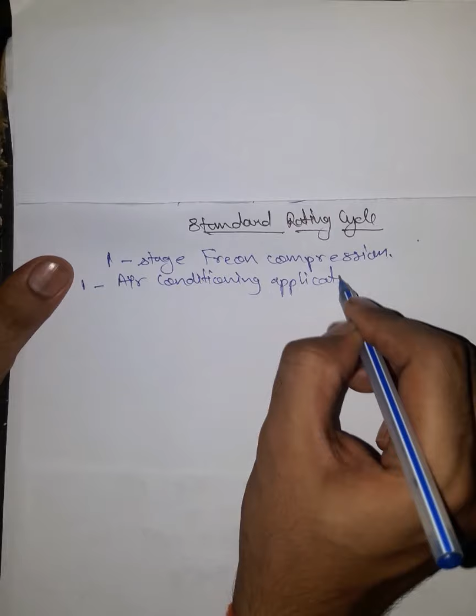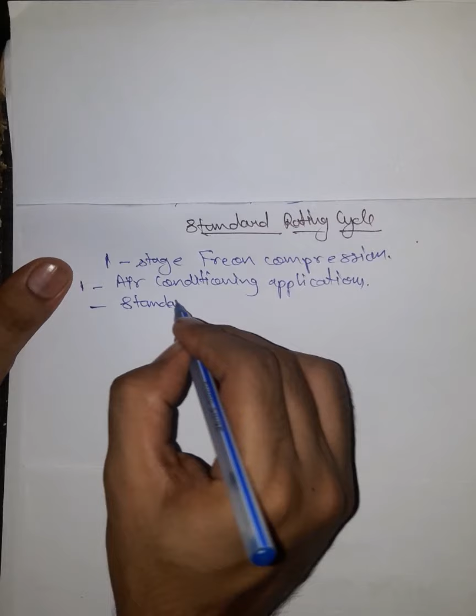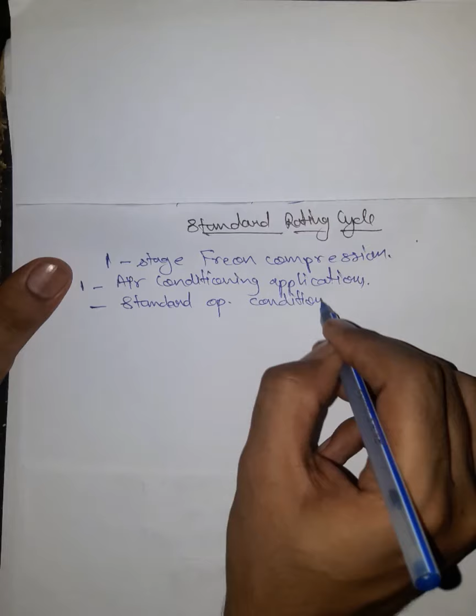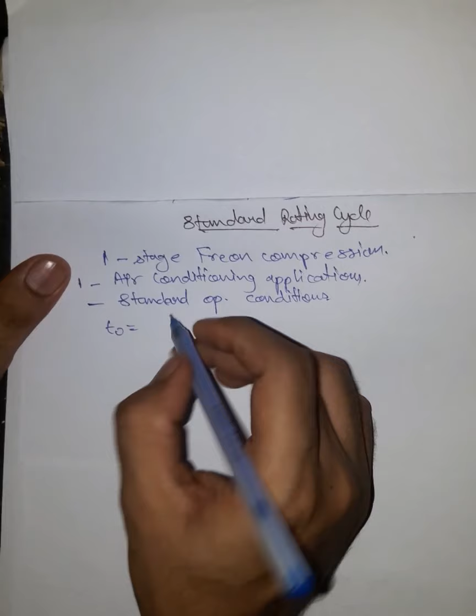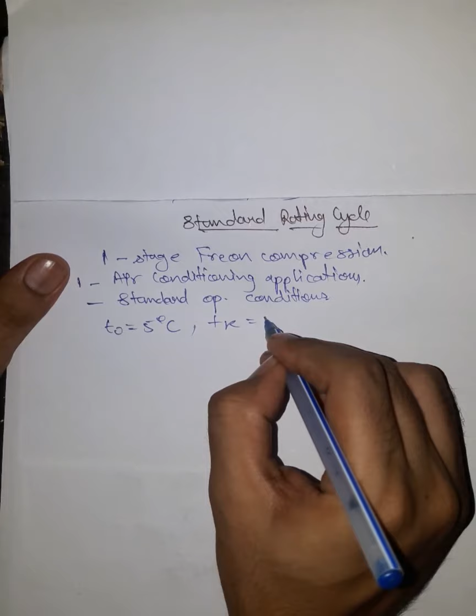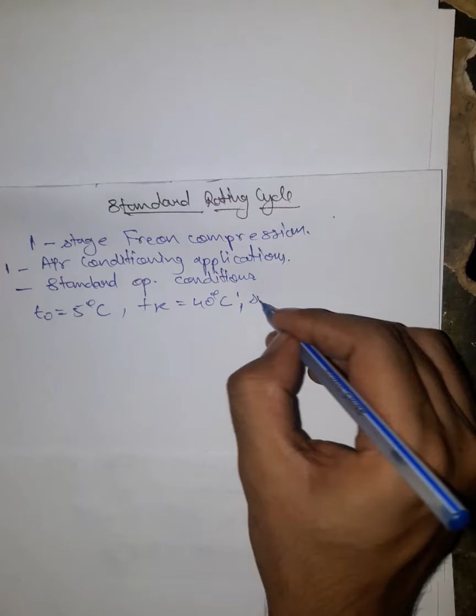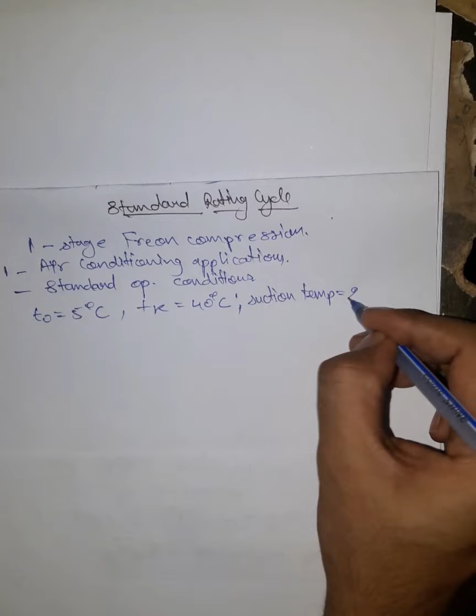Now for air conditioning applications, we have assumed standard operating conditions. And what are those standard operating conditions? T naught, that means the evaporator temperature, is assumed to be 5 degrees Celsius, and the condensation temperature is assumed to be 40 degrees Celsius, and the suction temperature, which is the temperature at the inlet of the compressor, is assumed to be around 20 degrees Celsius. So these are the assumptions for the AC application.